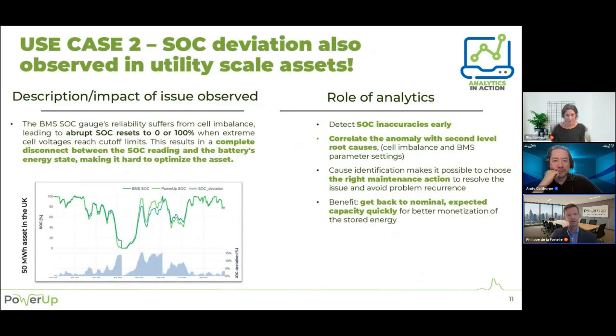As we can see in this 50 megawatt hour asset in the UK, the difference between what the BMS is measuring and what the battery analytics solution is measuring is even higher in this example than in the previous one, with differences going up to 15 or 16 points, which is of course a very large number. And we've seen even higher numbers in other cases, like 20, 25%.